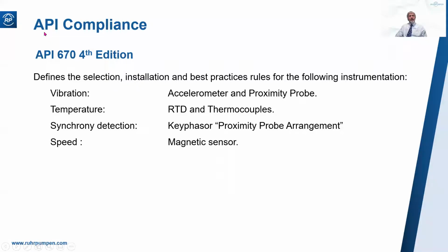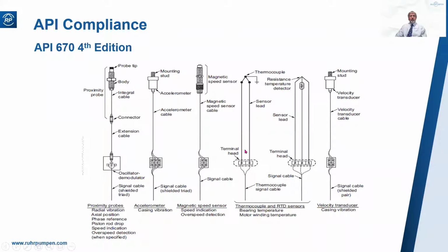So what do API say? API 610 references API 670, which defines selection, installation, and best practice rules for accelerometers, proximity probes, RTDs, thermocouples, Keyphasors, and magnetic speed sensors. I'll pause to let you look at this one. It's an extract from API 670. And all API pump suppliers are going to be compliant with API 670 for these instruments.